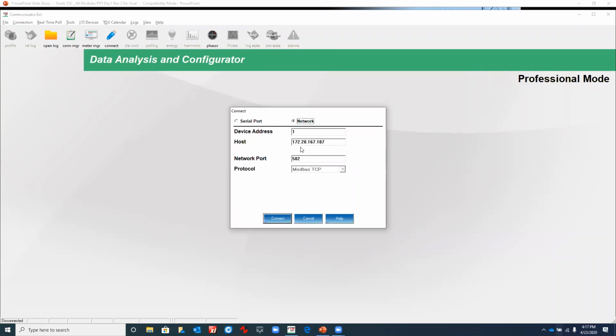For this type of connection, you will need the address of the meter, which defaults to 10.0.0.2, and that would go into the host field. The network port number remains the same. That's the default Modbus TCP port number, 502. And note this is a Modbus meter, so naturally 502 is the port number. The Modbus TCP option would be chosen, and you're pretty much ready to go. At this point we can click OK.